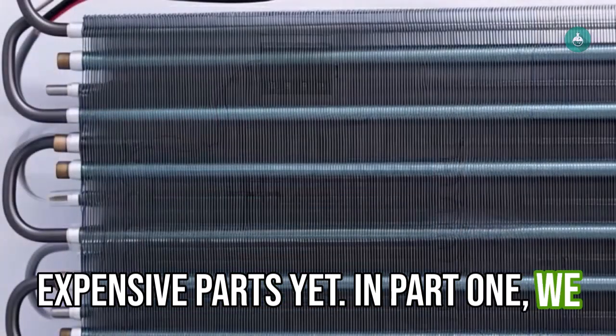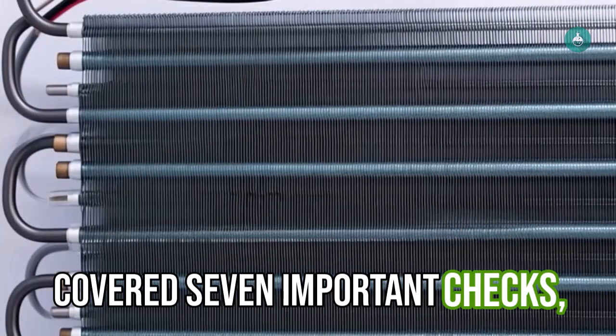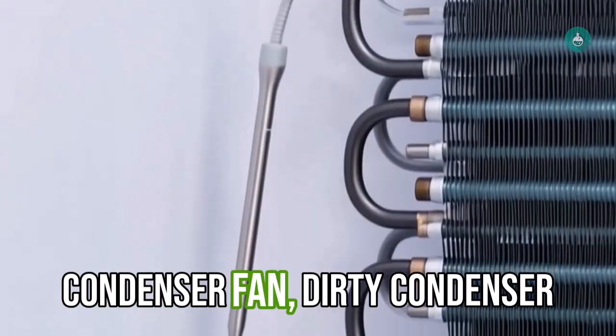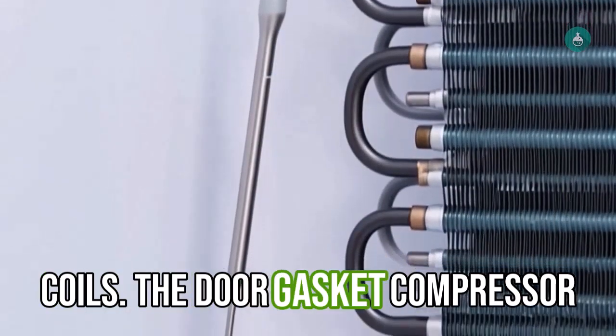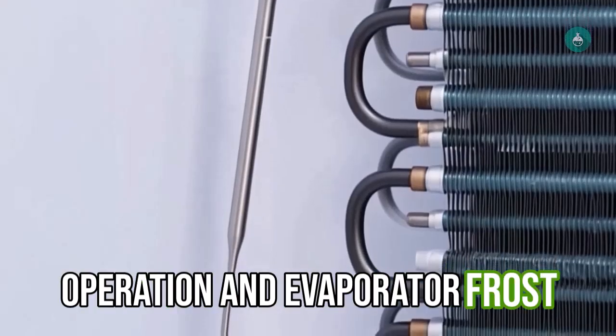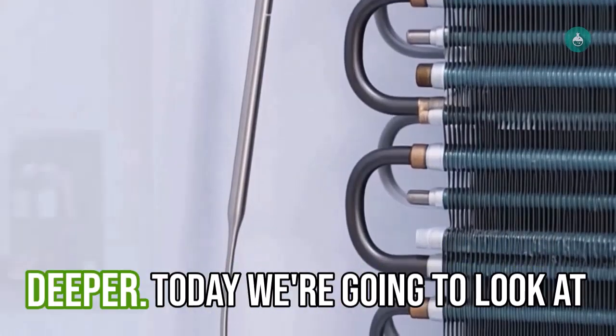In Part 1, we covered 7 important checks, including refrigerator temperature, the evaporator fan, condenser fan, dirty condenser coils, the door gasket, compressor operation, and the evaporator frost pattern. In Part 2, we're going deeper.